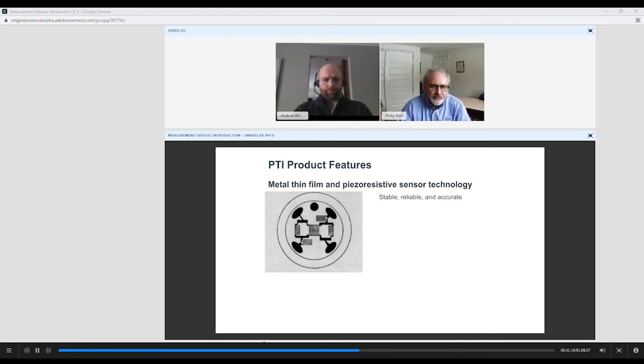So with the thin film piezoresistive sensing technology, one of the great things is that it's very stable. Long-term stability is less than or equal to 0.2% of span. And if you remember when we looked back at the percentages of span on dial-type Bourdon tube pressure gauges, some of them were up to plus or minus 5% of span. So where we use this is where you have very stable, long-term, excellent repeatability, again less than or equal to 0.1% of span.